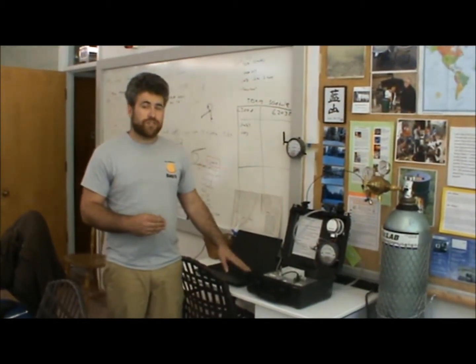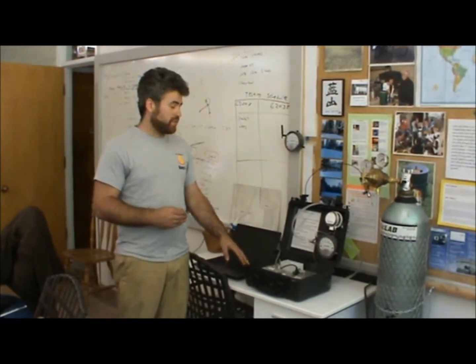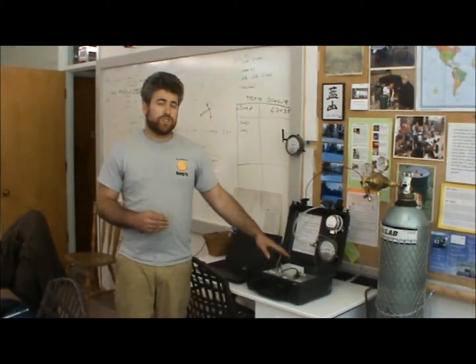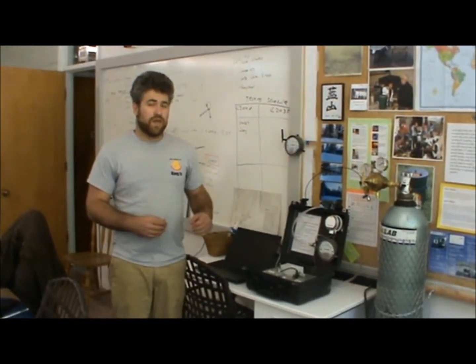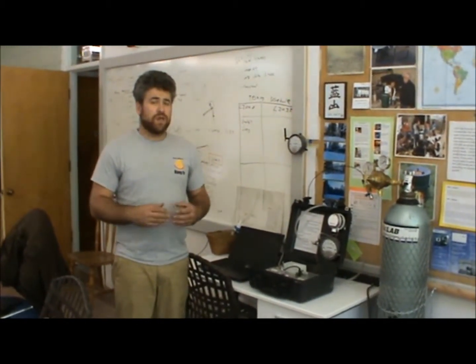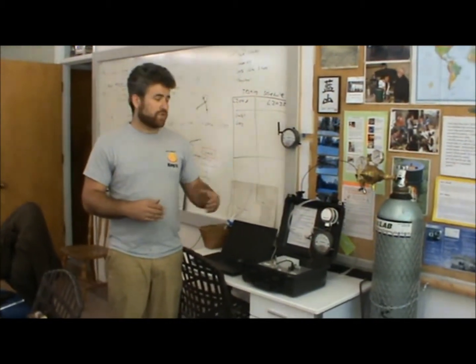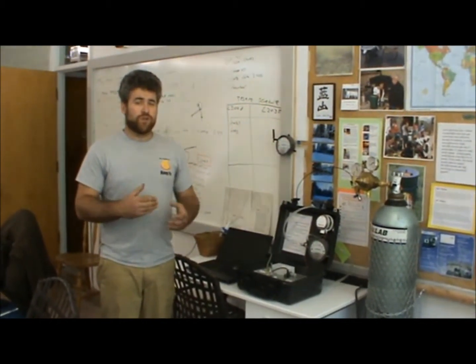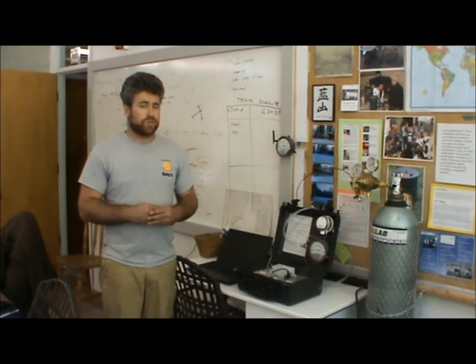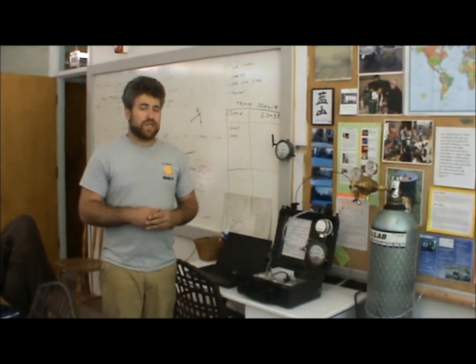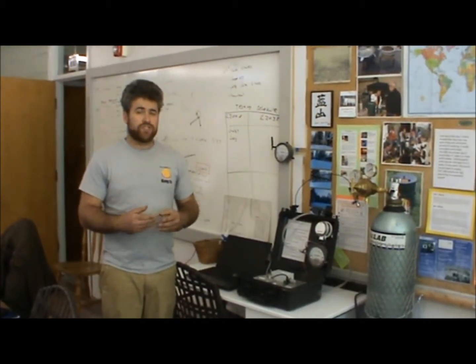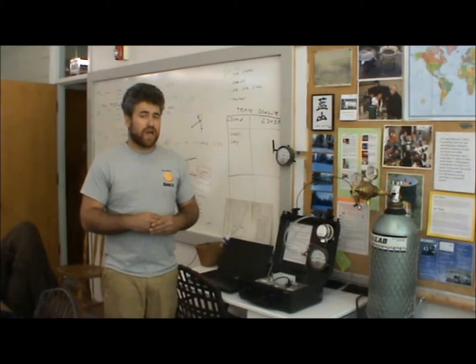This calibration procedure is only going to be good for the sensor boxes numbered 2022 and above. If you have an older sensor box, you'll need different tools. You'll especially need different gases to calibrate your sensor box. So if you're interested in calibrating one of those older sensor boxes, please contact Aprovecho for documentation and information on how to calibrate your older sensor boxes.